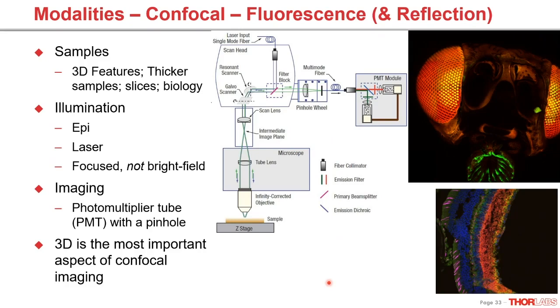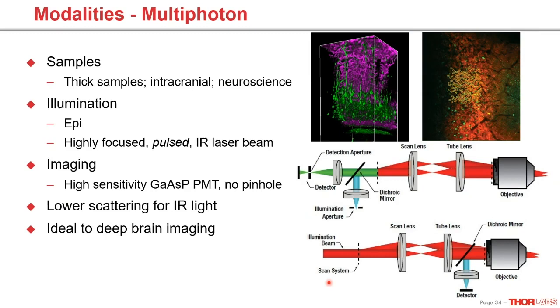Multi-photon is similar to confocal in many ways — it uses a scanning spot and collects photons on higher-sensitivity gallium arsenide PMTs. It uses a highly focused pulsed IR beam to induce fluorescence only exactly at the focal point, so there is no pinhole needed. IR light scatters less as it travels through tissue, skull, and other dense samples, allowing imaging at much greater depths. This will be covered in more detail in a later webinar.